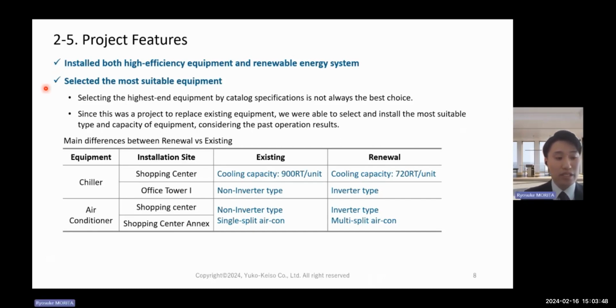The second feature is the selection and introduction of the most suitable equipment based on past operational results. Although installing high-efficiency equipment is an effective way to reduce greenhouse gas emissions, selecting top-of-the-line equipment based on catalog specification is not always the best choice. The type and capacity of equipment should be selected based on the operating load factor and other factors from actual past operations.